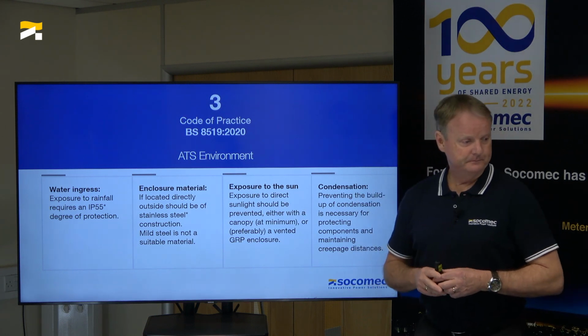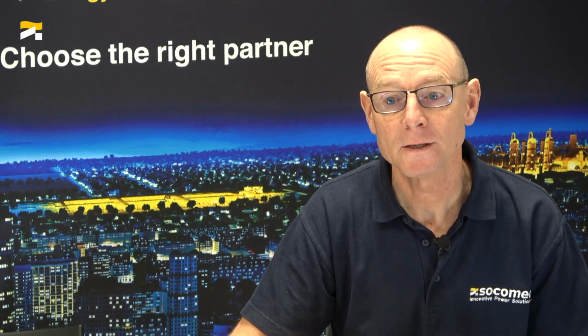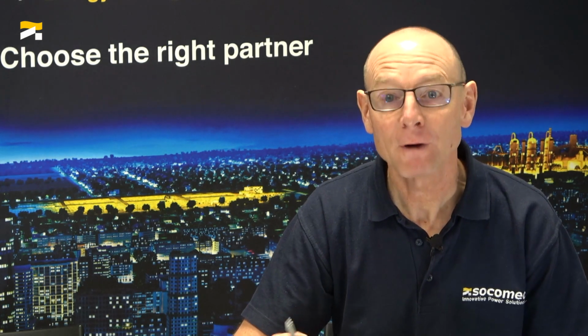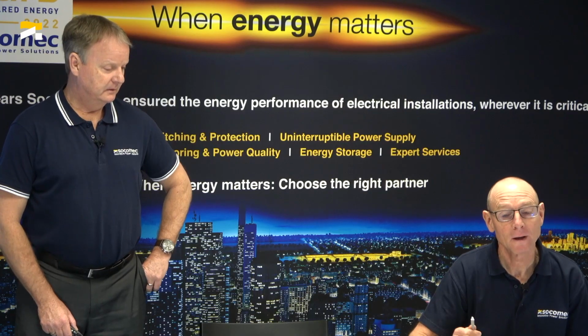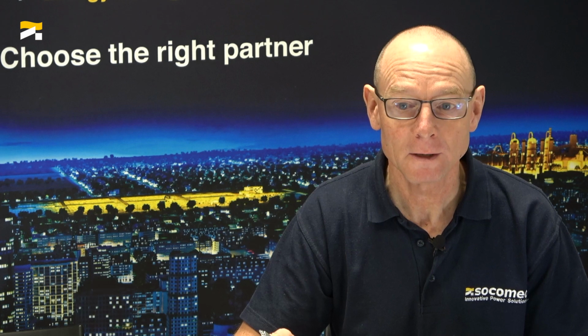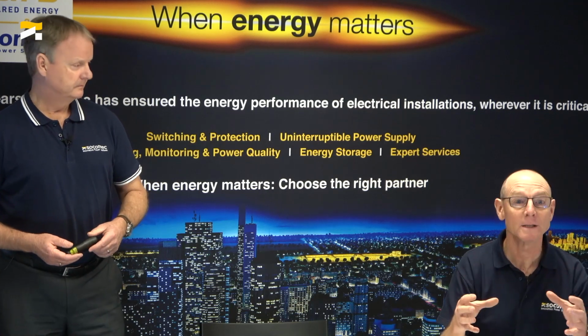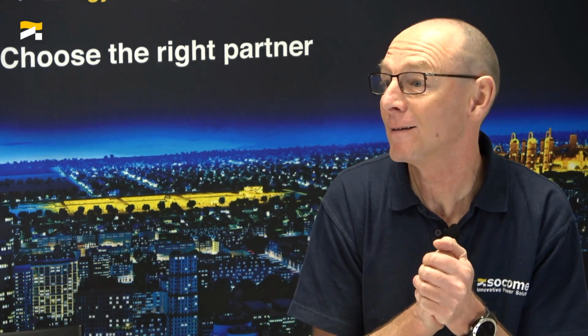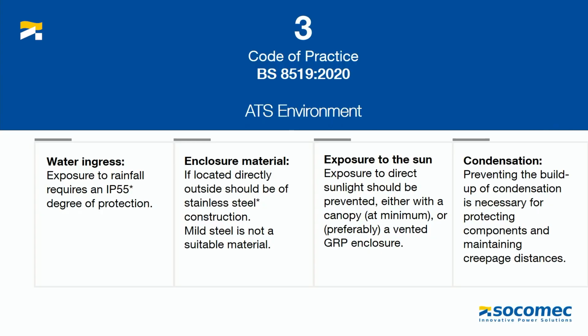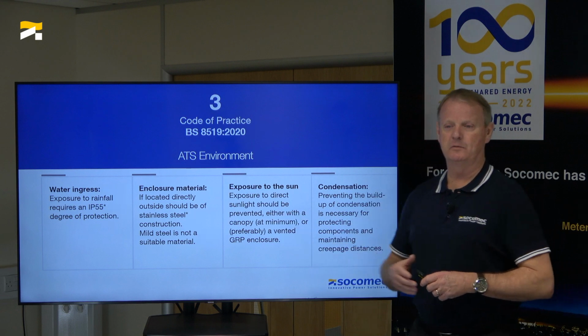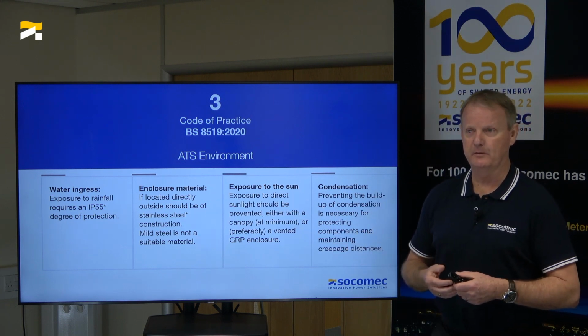This is another area where we see a lot of instances in the industry where they haven't considered the environment when specifying the product, and it does lead to problems when the items are being commissioned and deployed. A mild steel ATS on the roof in a GRP enclosure is fine, you don't have to go to stainless, but it's about understanding the environment where that ATS is going to be placed and ensuring you specify the right protection for it. I can think of numerous instances last year where that wasn't taken into account. It's all about safety, because if there's water ingress and it doesn't work, then the life safety service is not going to be able to work, are they?